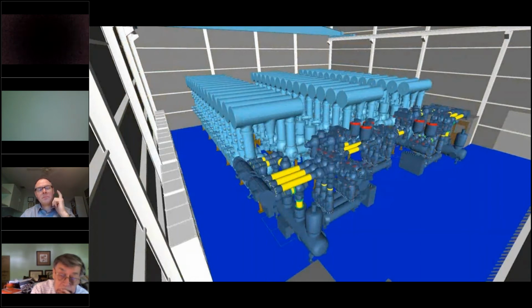And so, getting to the point of different equipment manufacturers and selections, what you could do is scan this physical space as the owner and then decide, not all switchgear is the same. So whose can fit, what space I have left, what options do I have within that existing space based on the number of bays and switchgear that I can put in there, and then how would it fit and how would it look. And so in this particular case, it was the same manufacturer that was extended. The light blue was the existing, the darker blue was the new switchgear, and it was able to be matched up very closely.